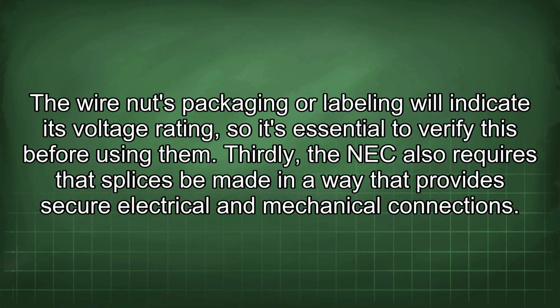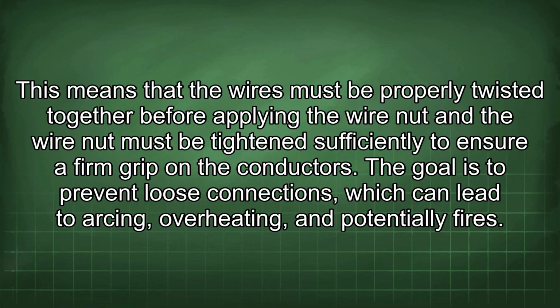Thirdly, the NEC also requires that splices be made in a way that provides secure electrical and mechanical connections. This means that the wires must be properly twisted together before applying the wire nut, and the wire nut must be tightened sufficiently to ensure a firm grip on the conductors. The goal is to prevent loose connections, which can lead to arcing, overheating, and potentially fires.